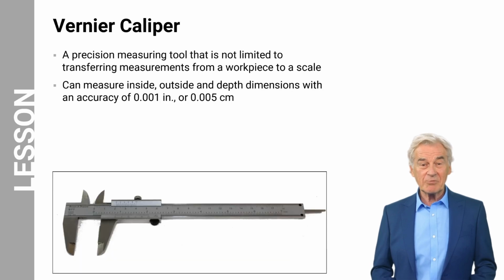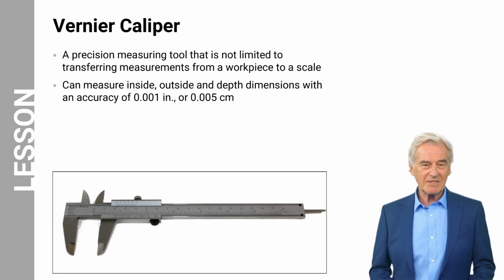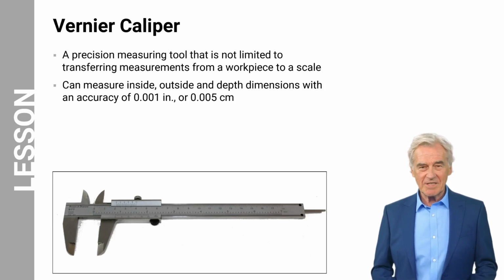The Vernier caliper is not limited to transferring measurements from a workpiece to a scale. It can actually be considered a true measuring instrument. The Vernier caliper is a precision measuring device. As discussed in the previous lesson, the Vernier scale on the caliper improves the accuracy of reading the instrument. Another advantage of a Vernier caliper is its ability to measure inside, outside, and depth dimensions, with an accuracy of 0.001 in or 0.005 centimeters.